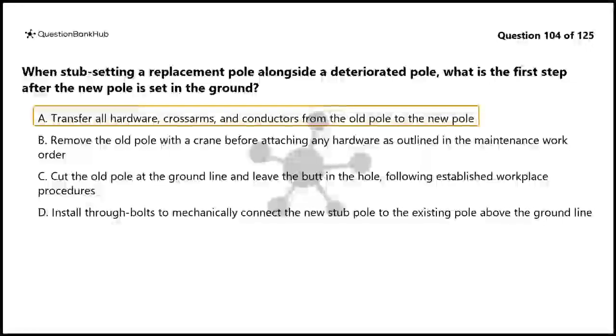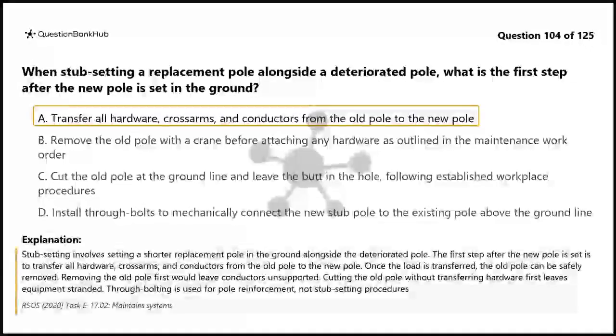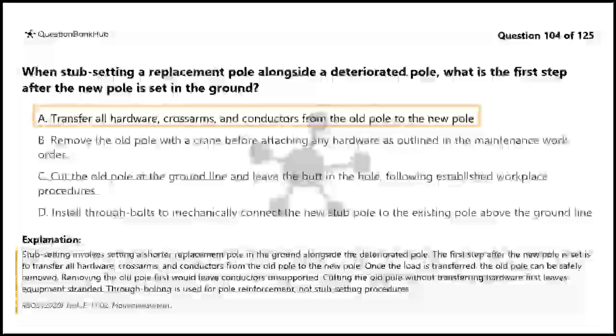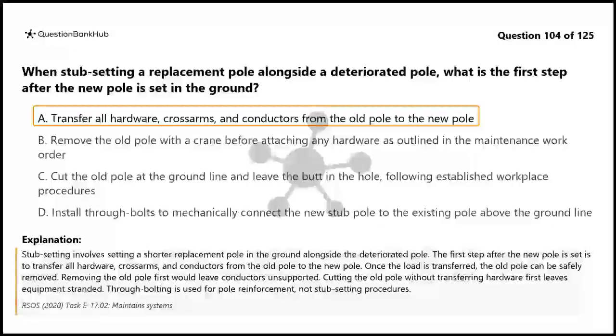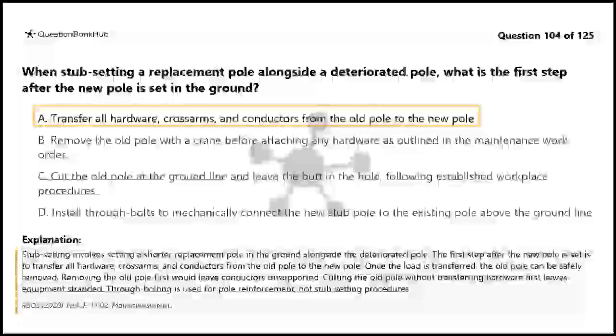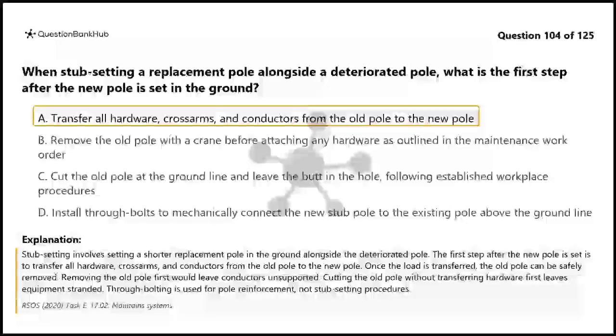The correct answer is A. Stub setting involves setting a shorter replacement pole in the ground alongside the deteriorated pole. The first step after the new pole is set is to transfer all hardware, crossarms, and conductors from the old pole to the new pole. Once the load is transferred, the old pole can be safely removed. Removing the old pole first would leave conductors unsupported. Cutting the old pole without transferring hardware first leaves equipment stranded. Through bolting is used for pole reinforcement, not stub setting procedures.